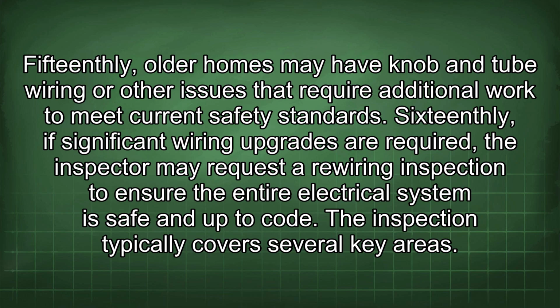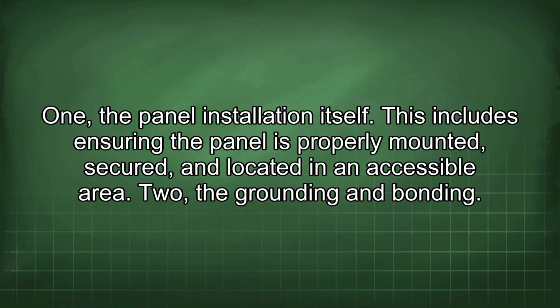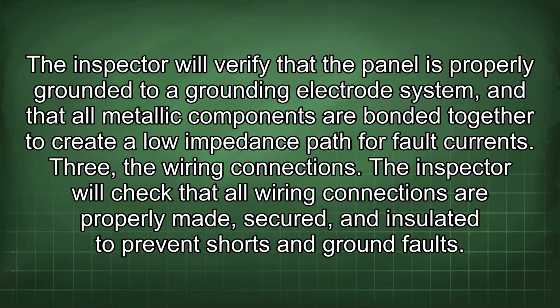The inspection typically covers several key areas. 1. The panel installation itself. This includes ensuring the panel is properly mounted, secured, and located in an accessible area. 2. The grounding and bonding. The inspector will verify that the panel is properly grounded to a grounding electrode system and that all metallic components are bonded together to create a low impedance path for fault currents.